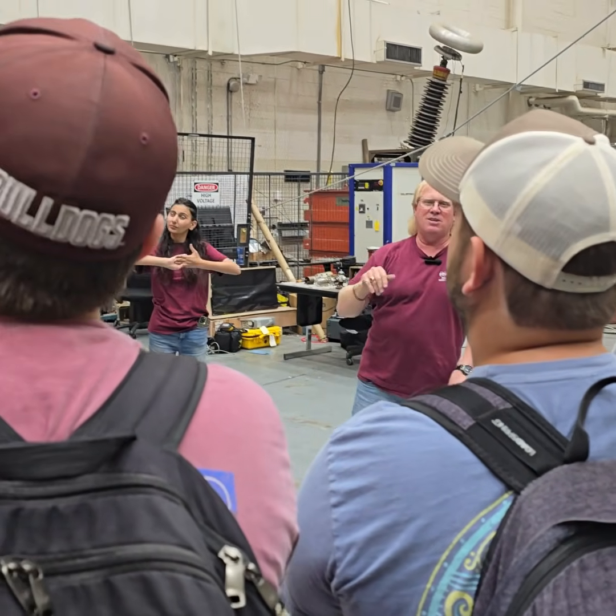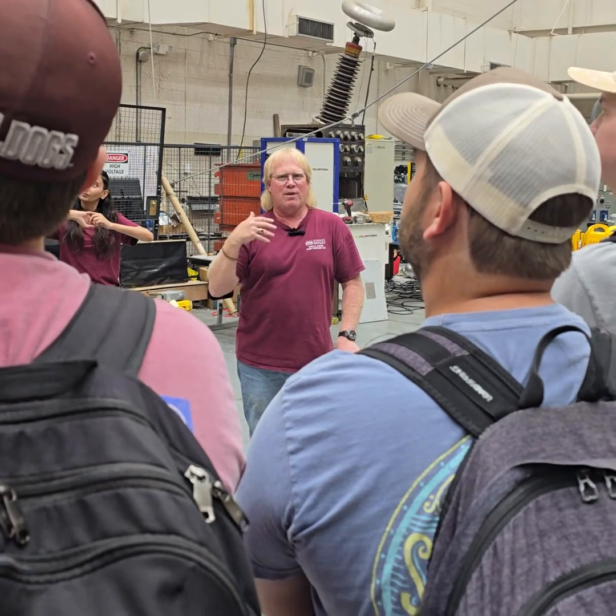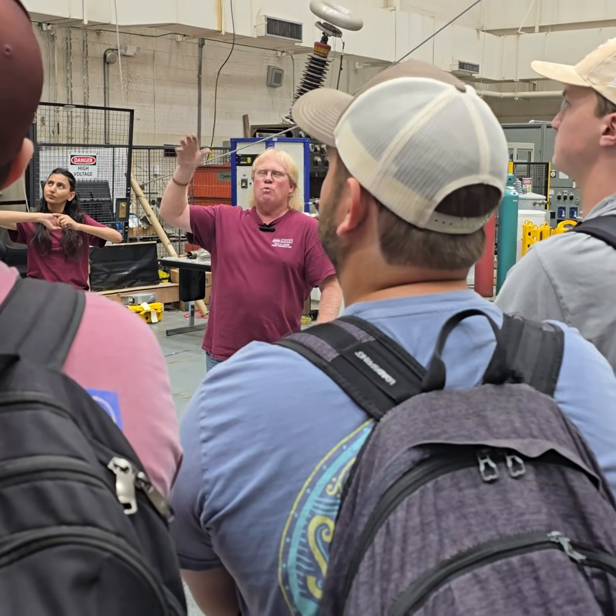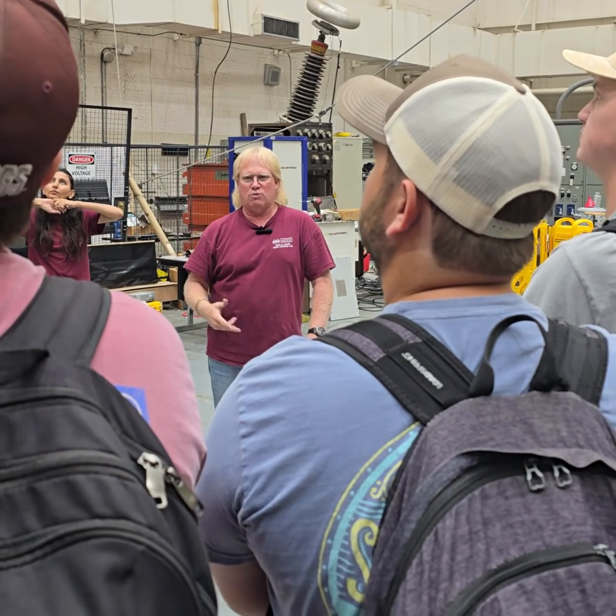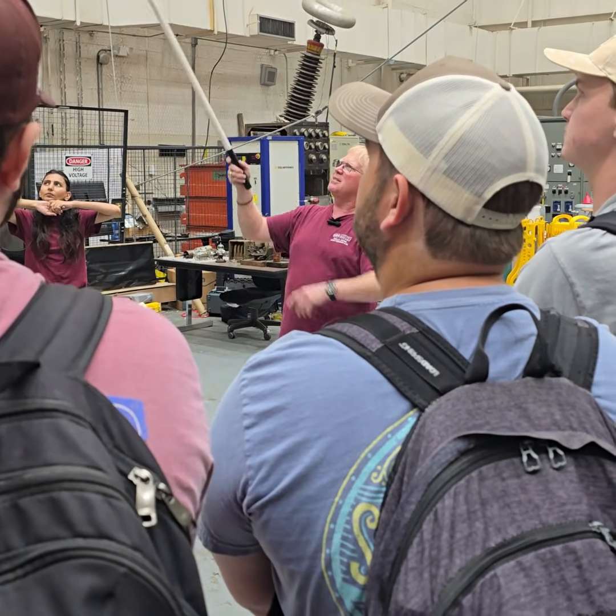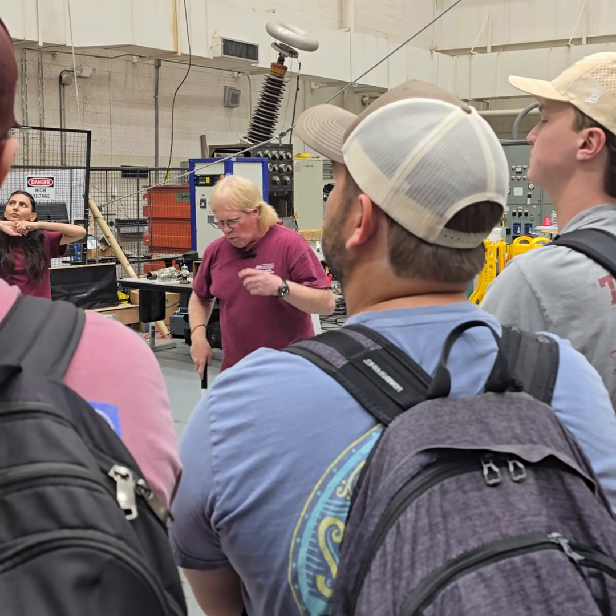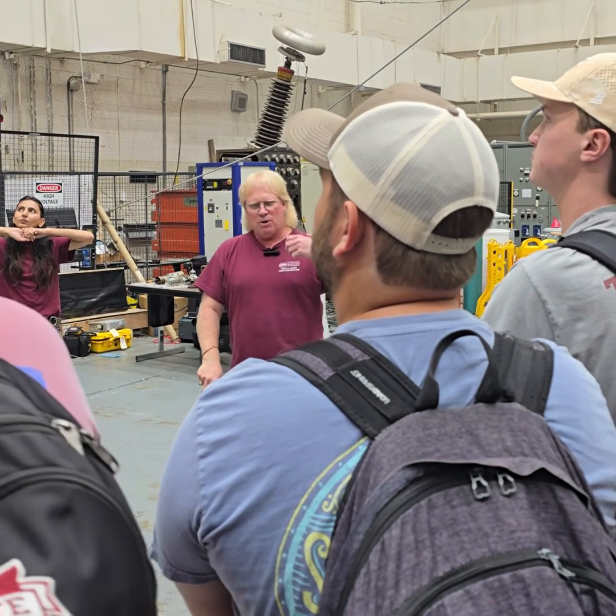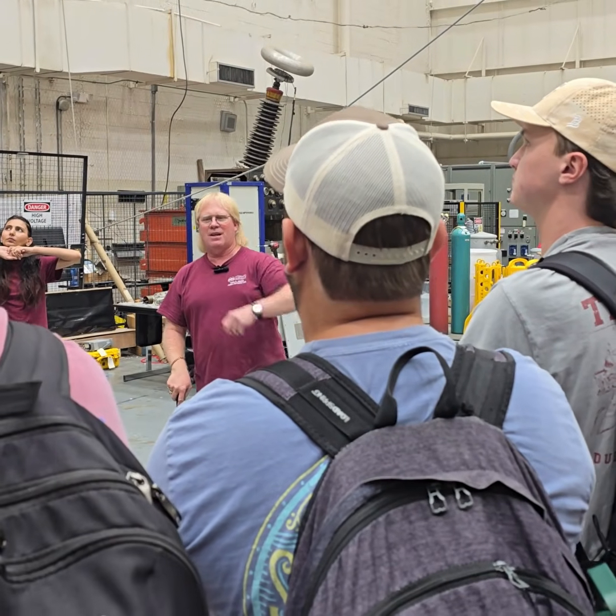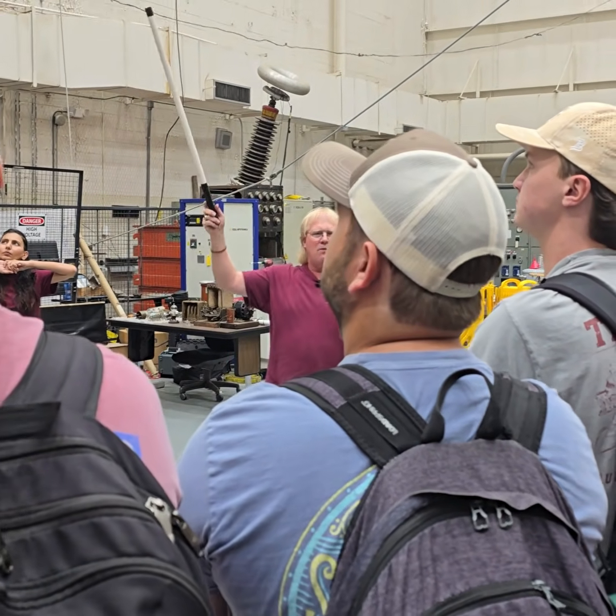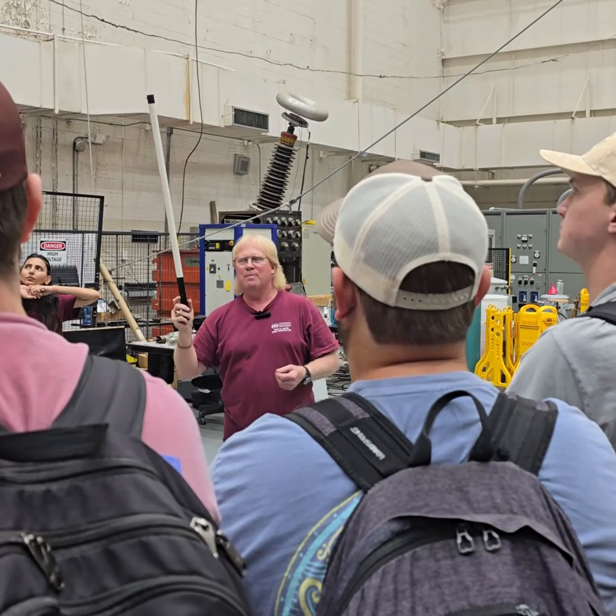So we study these things to make sure that they perform the way they're supposed to, and then we can see what they can actually take over voltage-wise. So what we're going to do today is actually make this one fail. We're going to start ramping the voltage up, and we're going to go higher and higher and higher until it breaks down. Now, this will be an example of a solid insulation breakdown.